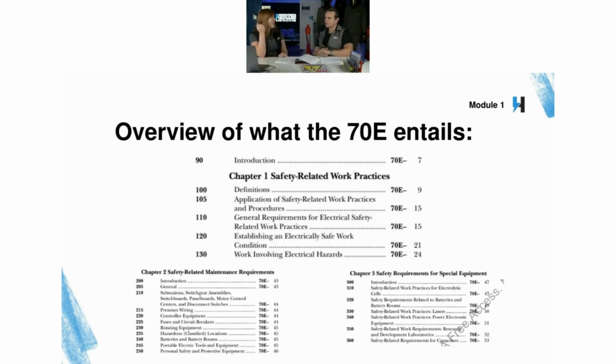You were doing great. Caitlyn, you can take this one. Okay. Well, there's 8 steps according to the NFPA 70E. Those would be determine all sources, make sure that you identify everything, and then properly interrupt the load current. So shut off the equipment, and then open up the disconnecting devices. Wherever possible, visually verify that the blades are actually disconnected or that drop type breakers are fully withdrawn. Release the stored electrical energy, block or relieve stored non-electrical energy, so gravity or something like that. Gravity is a very often overlooked lockout hazard. Apply your lockout tagout devices.